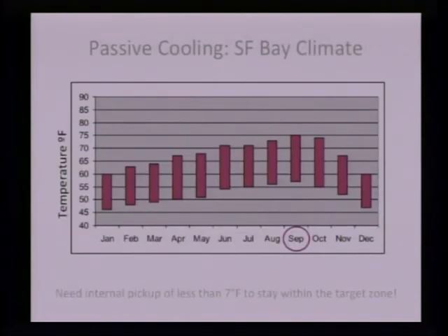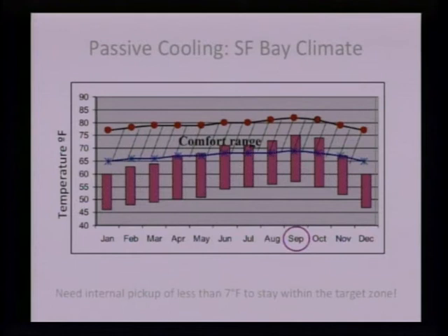The assumption here was that occupants would actually have an expanded comfort range based on the seasonal changes in outdoor ambient conditions, which follows a conventional wisdom that in the summer people are adapted to warmer conditions, in the winter people are more prepared for cooler conditions. The control regimes in buildings shouldn't have an ad hoc set point that's held throughout the year, but should modulate to reflect those seasonal changes in climate, which has huge energy savings if you consider the savings that could be achieved by less air conditioning hours, less heating hours to hit those set points.